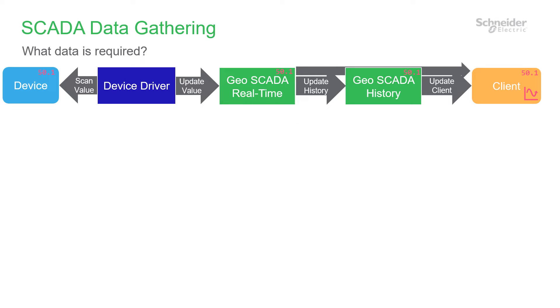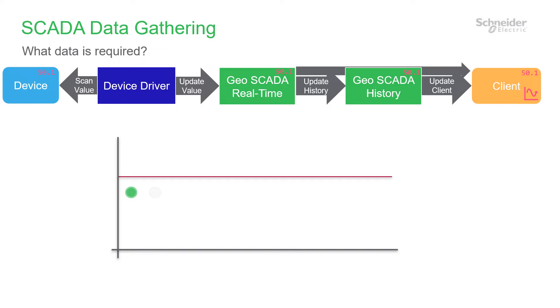So what's the answer to this? Firstly, recognising that SCADA, and particularly GeoScada, is an information handler. An unchanged value can be ignored. If a value doesn't change, we just don't need to know. But if the communication status or quality changes, or the value changes by a significant amount, then we do need that, and quickly. So you need significant change values where the change carries information, and alarm threshold crossings where you need to know quickly if there's a problem, and also some slow periodic values perhaps for reporting — the other values are not relevant.